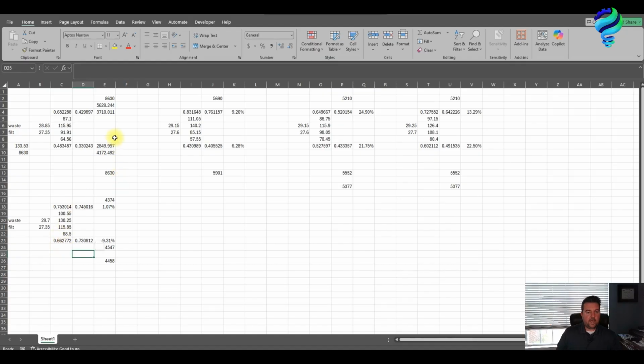If you look at the progression—1, 2, 3, 4, and now this is my fifth—these numbers on top are that constant variable I mentioned that converts the pulses to gallons. You can see we started off high, which was the recommended setting, and we've come down gradually over time. Basically I'm trying to get closer, because every time the system was undershooting what was actually put through.